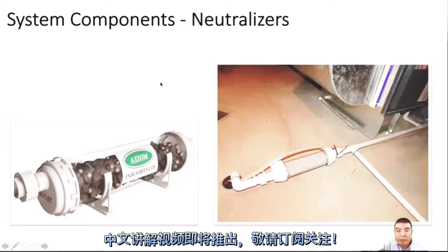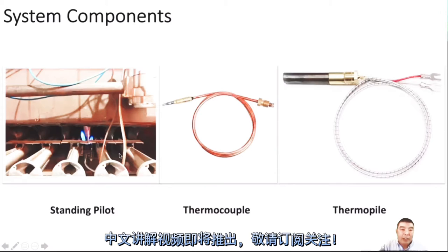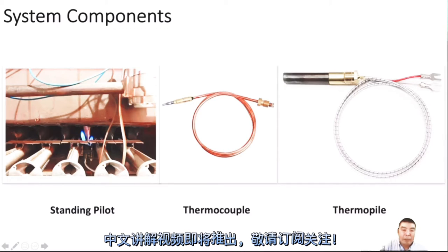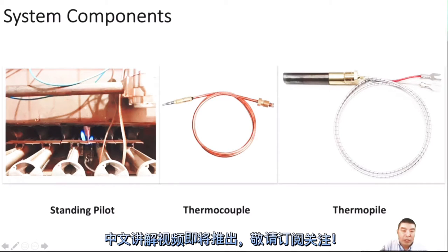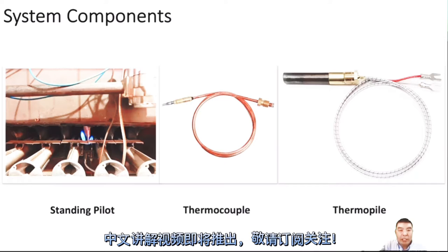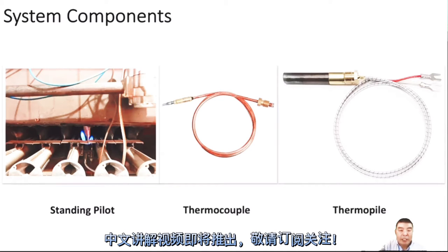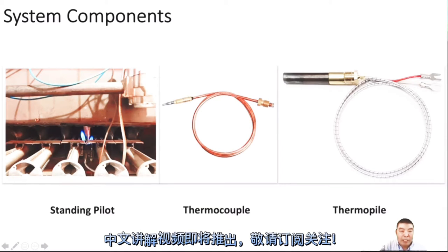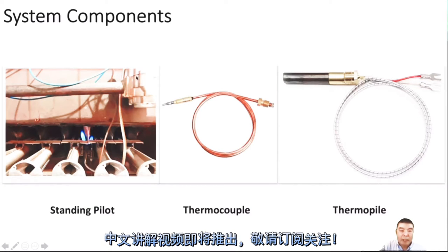This is a standing pilot on a category one furnace. This small flame is always there — it doesn't matter if it's summer or winter, whether we need heat or not. This just makes the furnace efficiency lower. We can see this aluminum pipe goes to the gas valve. Normally the gas valve has a knob with off, on, and pilot positions. We turn it to pilot and press down so gas comes out of this small pipe, then use a barbecue lighter to light the pilot and hold that knob for about 30 seconds.